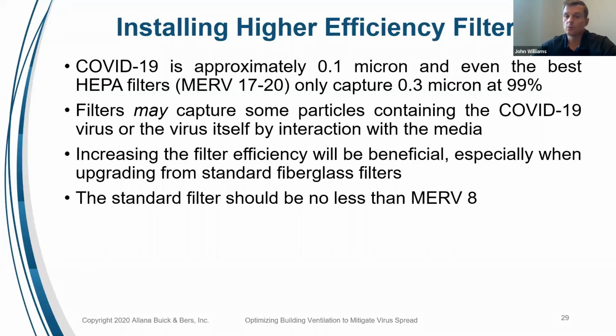Therefore, we do think increasing filter efficiency is a recommendation, and we do not recommend anything less than a MERV 8. Anywhere between a MERV 8 and a MERV 13 is typically where 95% of all those systems out there are going to land in our recommendations for filter efficiencies.